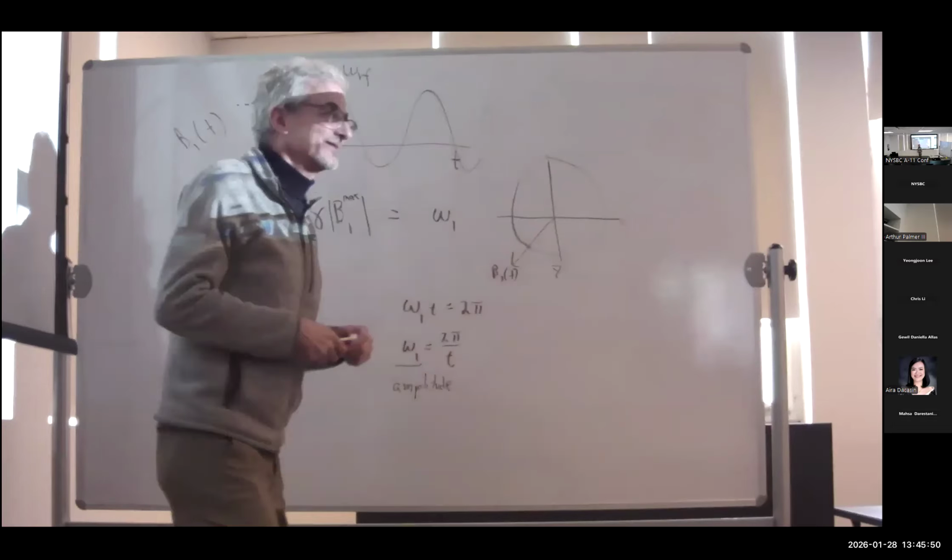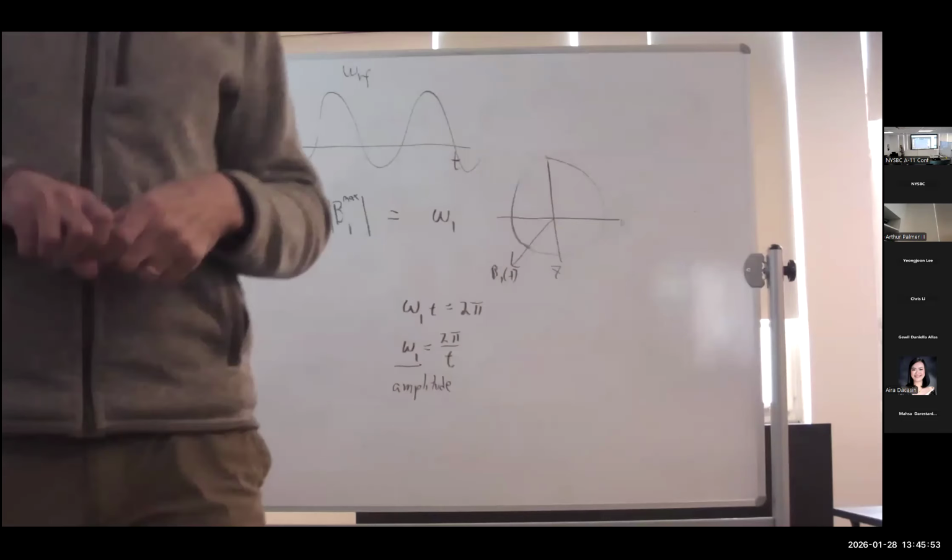And I just wanted to add something: the power should scale like gamma squared, because the voltage or the B1 field should be like gamma, but the power is the square of that. But you don't really see that because the efficiency of the probe goes down as you go up in frequency, it's harder and harder. So in reality, it is almost linear in gamma. But if the probe worked perfectly at high frequencies, it would be an astonishing difference, I think, in the power needed to get to the same omega 1.